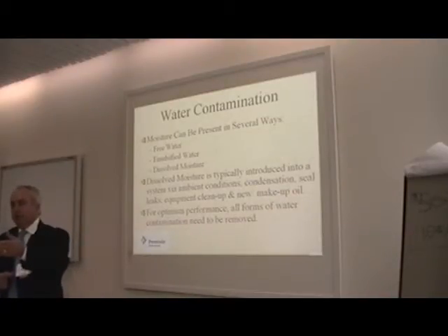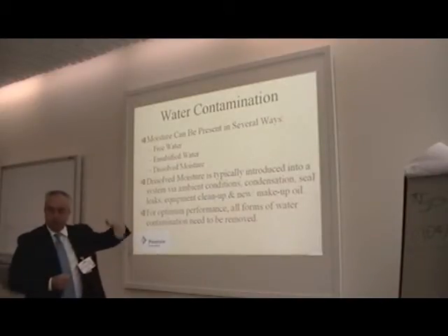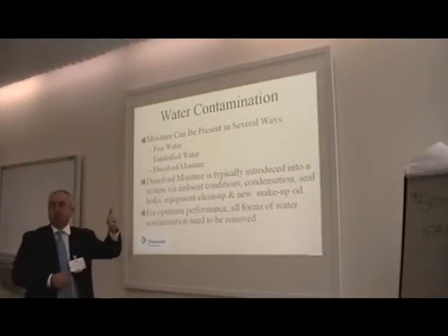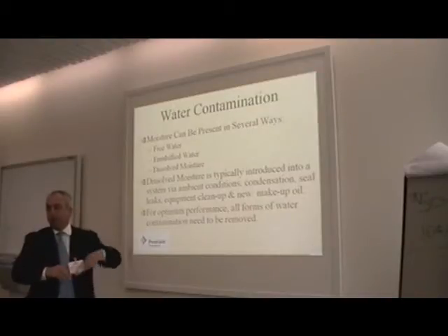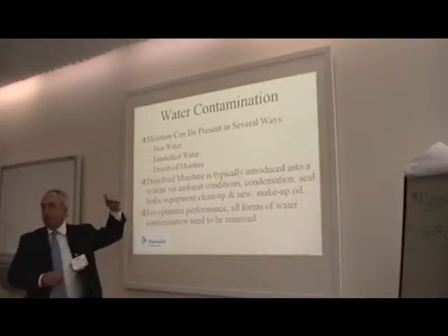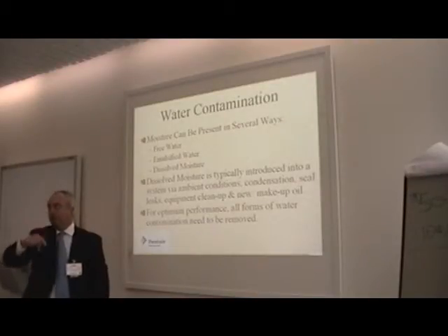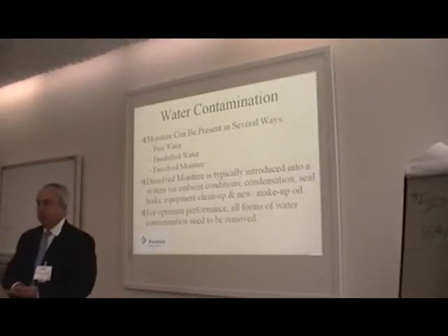And they may have a similar problem, because we've taken that chart of the moisture content of the oil, which was obviously declining, but every time they changed load on that turbine, it skyrocketed. When that turbine went from idle or low level to a high load, they'd put in 300-400 parts per million of water, and then it would clean it back up. Every time the load changed, we saw a spike in water. They said that's indicative of that particular turbine. They have 7 turbines on site. The other 6 don't have the problem. So it's something to do with that unit.